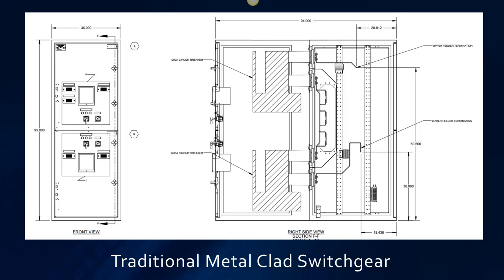Medium voltage metal-clad switchgear. It was invented and standardized around the same time as the vacuum breaker was invented. And it is a very robust system. It is also very particular in its standard. The metal-clad standard tells the manufacturer how to build the medium voltage gear. It does not leave any leeway for where the horizontal bus goes. And if you can see in this drawing, this is where the horizontal bus is here. The horizontal bus has to be barriered, and it has to run through the center of the gear. That has to be barriered from this rear section, which is the cable compartment. And the bus also has to be barriered from the breaker compartment. They have to be 3 individual barriered compartments. And you can't get this done in less than 94 inches.